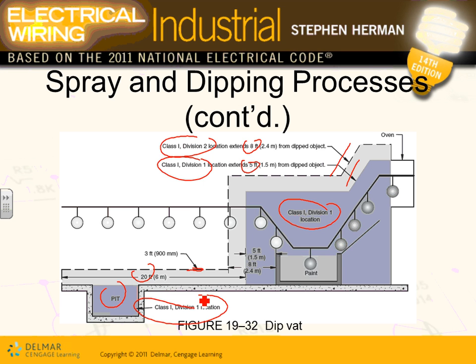So who cares? When you design a dipping, painting, or spray process, Adam, you are to take this into consideration. You have a lot of coordination to do with your chemical engineers or whoever is designing it, to avoid putting electrical equipment in the places where it could ignite the whole place. Do you guys see the gravity of this? You have flammable stuff. You put an ignition there and you get yourself a big fire.